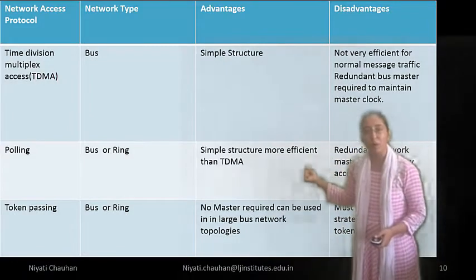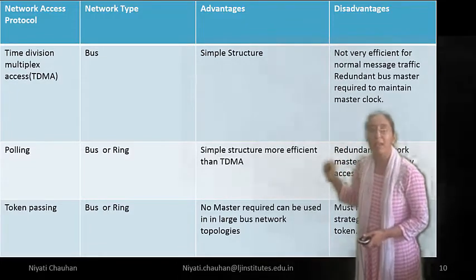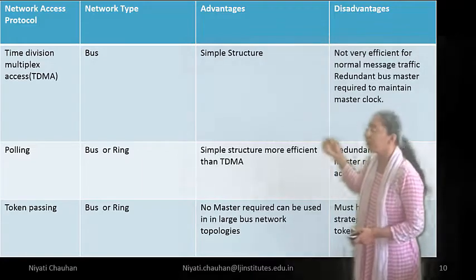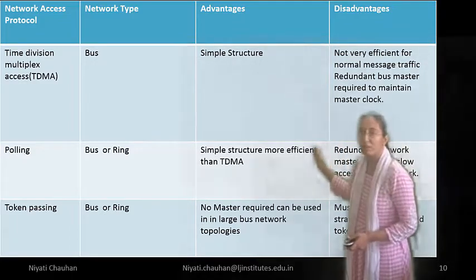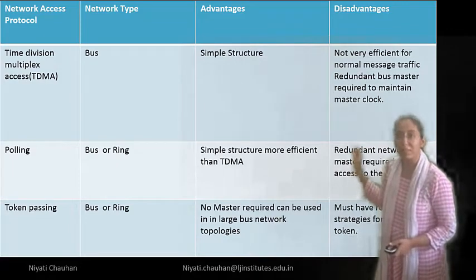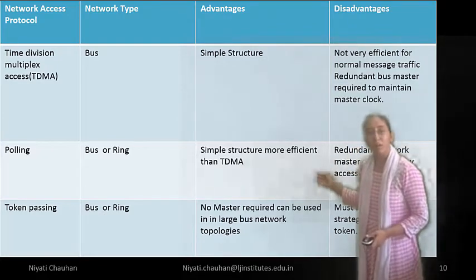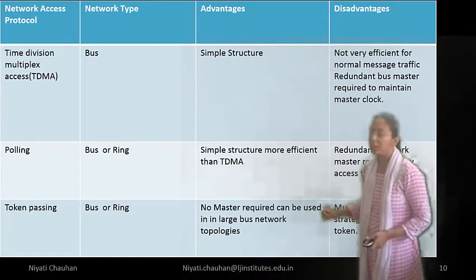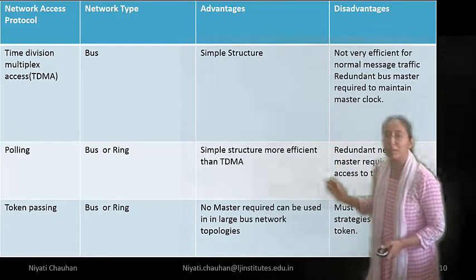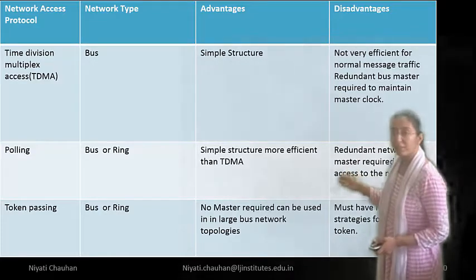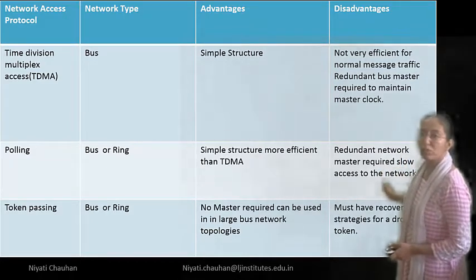In network access protocols, we discuss different protocols. First: Time Division Multiple Access (TDMA), network type — bus. Advantage: simple structure and ease of use. Disadvantage: not very efficient for normal message traffic; requires a redundant bus and a master to maintain the master clock. Second protocol: polling, using bus or ring network. Advantage: simple structure, more efficient than TDMA. Disadvantage: redundant network, master required, slow access to the network.